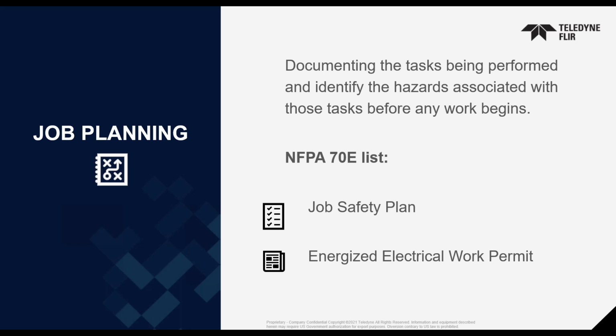Those are typically part of an energized electrical work permit, but there's also a job safety plan—a separate document detailing how you'll handle the job plan and job safety for that activity. I wanted to bring these up to set a foundation for discussing the differentiation between 70E and 70B. We'll see elements in 70B that reference back to 70E components, so as you have conversations with customers about PPE requirements and developing a good safety program around electrical maintenance, keep that in mind.